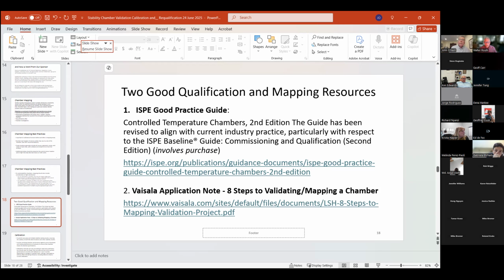But before you move on to the calibration topic, there are two good related questions on OQ and PQ. The first is, if the PQ was done with a full load and the layout was set up, could the layout of the freezer be changed after the PQ? And if so, would a new PQ need to be performed? I'll give the user aspect of that, and then we'll ask the rest of the panel.